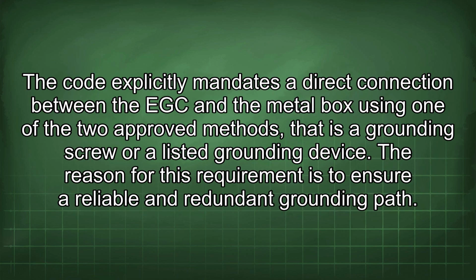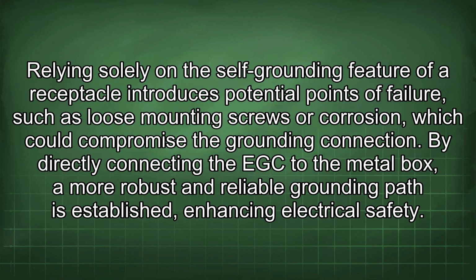The code explicitly mandates a direct connection between the EGC and the metal box using one of the two approved methods, that is a grounding screw or a listed grounding device. The reason for this requirement is to ensure a reliable and redundant grounding path. Relying solely on the self-grounding feature of a receptacle introduces potential points of failure, such as loose mounting screws or corrosion, which could compromise the grounding connection. By directly connecting the EGC to the metal box, a more robust and reliable grounding path is established, enhancing electrical safety.